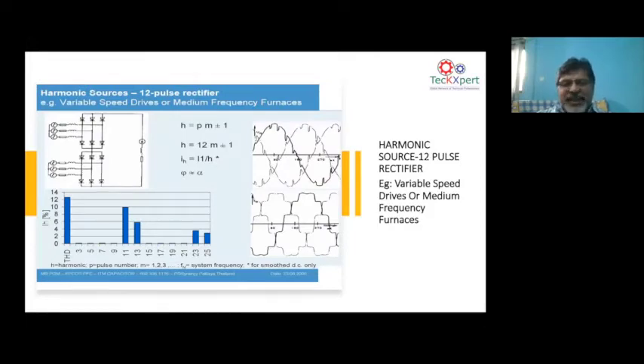If you go to the 12 pulse, that's another way. Many times people say, I have a 12 pulse drive, so I have no harmonic problem, I don't have to worry about harmonic problems. Yes, to an extent, but a 12 pulse drive also causes harmonics which are of higher order. You can see here the 11th harmonic, 13th harmonic, 23rd harmonic, 25th harmonic. And you can also see the voltage waveform has more notching compared to the 6 pulse, where we didn't see so many notches on the voltage waveform. So as you go to the 12 pulse drive VFD, you will see more notches on the voltage, and you see higher frequency harmonics also. Now, this is very important to note, because now, okay, 11th and 13th, it's fine.